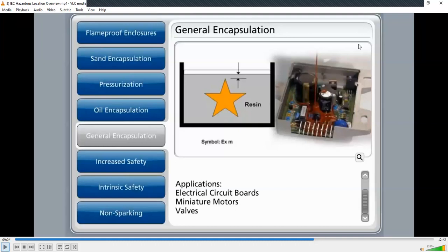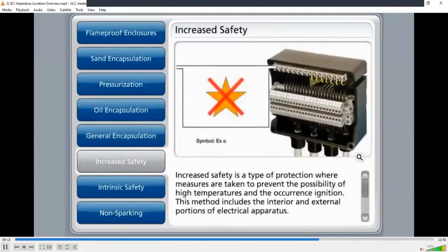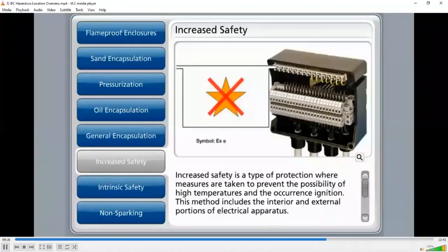The general application for this protective method would be used for electrical circuit boards, miniature motors, and valves. Increased safety is a type of protection where measures are taken to prevent the possibility of high temperatures and the occurrence of ignition. This method includes the interior and external portions of the electrical apparatus. The general application for this protective method would include connection and distribution boxes, luminaires, measuring instruments, and devices that do not normally produce ignition within operation.